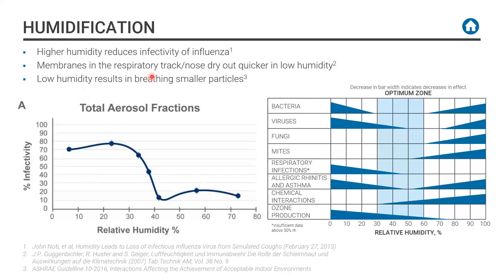Factor number two is that the membranes in the respiratory tract dry out in lower humidity, and that's our first line of defense. Many of us use a saline solution when we go on airplanes so that our respiratory tract is better equipped to remove what's in the air. The third one, which gets a lot of us nervous, is that low humidity results in breathing out smaller particles. As you breathe out, they start evaporating, become buoyant, and may become aerosolized, so that 6 feet may go farther than 6 feet. The question is, when they become aerosolized, are they as potent as they were as a droplet? The jury is still out on that. This is a standard chart in the industry showing that infectivity of viruses, bacteria, and other allergens is reduced when you get to 40 to 60% RH.